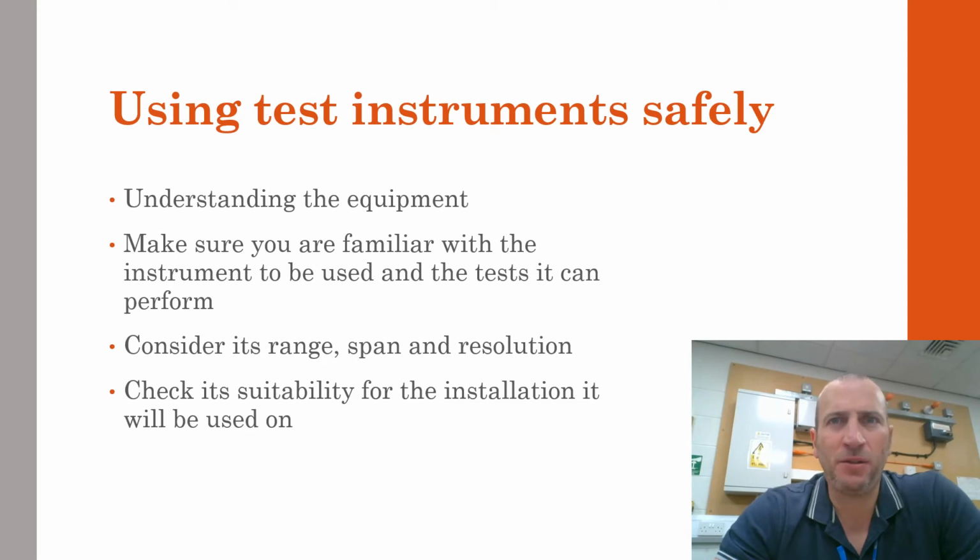which measures impedance, which is similar to resistance, but includes reactive components. PFC tester, which measures fault currents in the thousands of amps range or kiloamps. And the RCD tester, which records tripping times in thousandths of seconds or milliseconds.